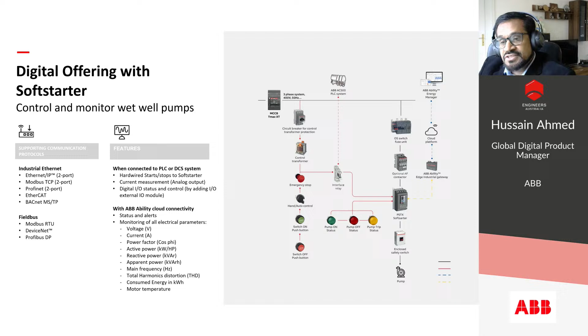Next, we look at how our soft starters can be connected digitally. There are two aspects: we can connect our soft starter to a cloud-based system, and we can connect it to PLCs and DCS through various field buses, including Modbus RTU, DeviceNet, and Profibus. There are address ranges to ensure PLCs, DCS, and digital systems get parameters from the soft starter, such as voltage, current, power factor, and whether the pump is in dry run or clogging. These parameters are stored in the soft starter, and users can access this data in PLCs and DCS once connected via Modbus RTU, DeviceNet, Profinet, and so forth.